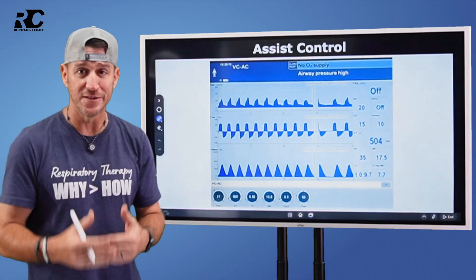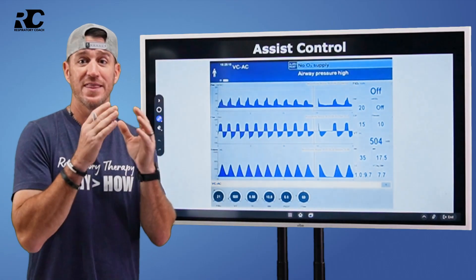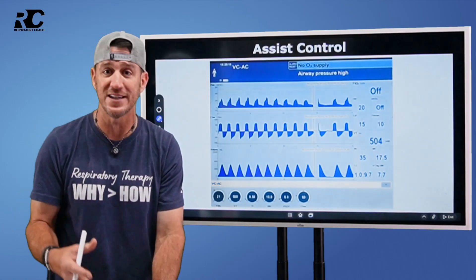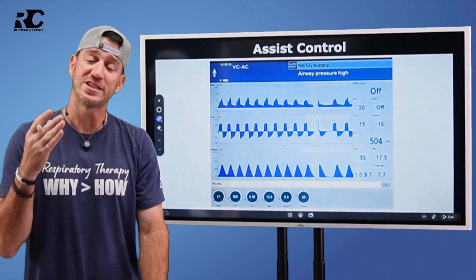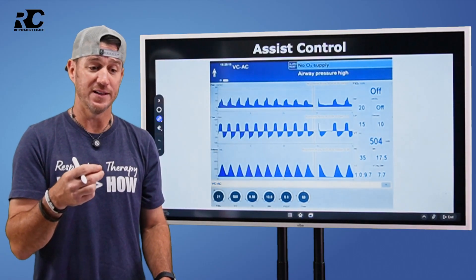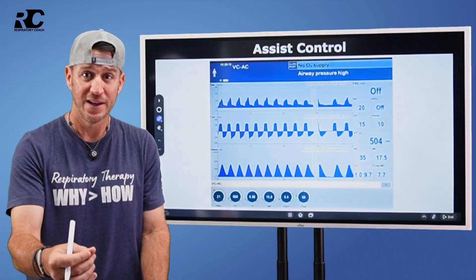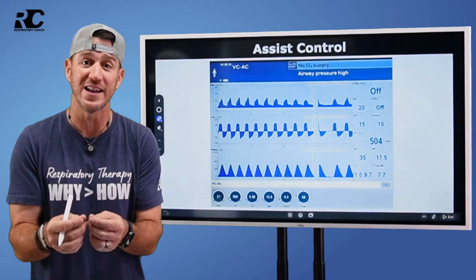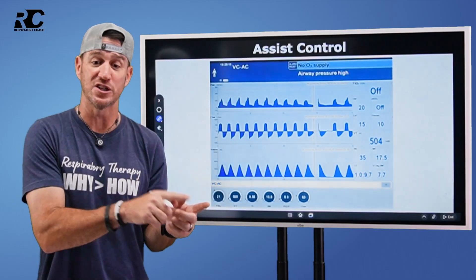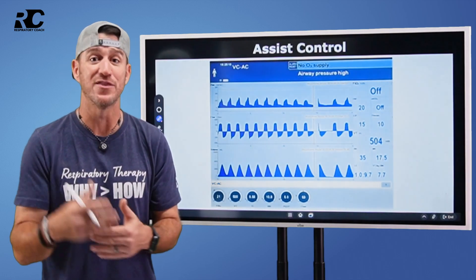What assist control tells the ventilator is: you have a job to do, and your job is to deliver this breath this many times a minute. You set all the parameters on the ventilator. But the ventilator has to know what to do when a patient effort is detected. So when the patient tries to initiate a breath — remember sensitivity — the purpose of sensitivity is to allow the ventilator to detect a patient effort. It's very important to have sensitivity set correctly, because that's going to trigger the ventilator to allow the patient to do something, or to not allow it and have the vent do something instead.